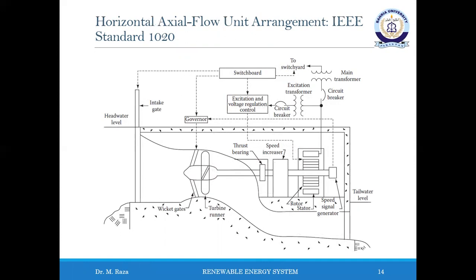The induction generator draws its excitation current from the electricity system and thus cannot be used in an isolated power system. The generator output is connected to terminal equipment via cables, bus bar, or isolated phase bus. The terminal equipment comprises current transformers, voltage transformers, and surge suppression devices. The generator circuit breaker and associated isolating disconnecting switches are used to connect and disconnect the generator to and from the power system. The generator circuit breaker may be located on either the low voltage or the high voltage side of the generator step up.